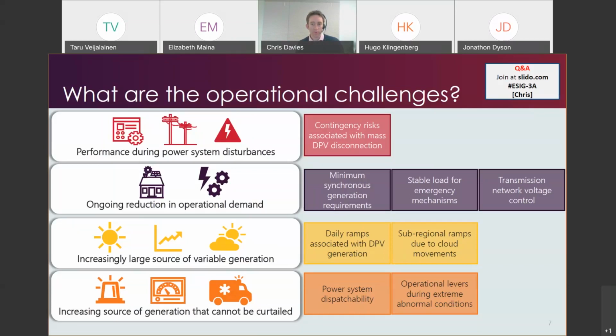Next is having enough stable load available for emergency under-frequency load shedding for those schemes to be able to work properly. And lastly, increasing challenges in the management of transmission network voltages. And I think Hugo might also touch a little bit on that. We also see challenges associated with the variable characteristics of distributed PV. So firstly, there's the management of the increasing daily ramp requirements as solar comes online in the morning, goes away in the evening, and accounting for that in the dispatch of large generation. And then as a further complication, how you manage sudden cloud movements over metropolitan areas that can significantly exacerbate the rate of those ramps that need to be covered by your dispatchable fleet.